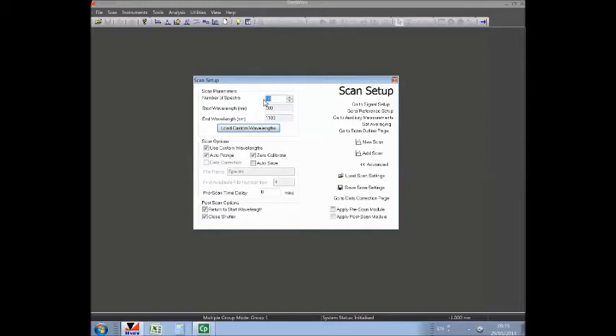It's also beneficial to take the average of a number of scans. It will give us confidence that this measurement is stable and the system is stable, and should there be any noise in the measurement, which we don't necessarily expect there will be, then averaging a few scans will average out the noise, which would otherwise appear, since this is the calibration measurement, in all of the future measurements done with this system.